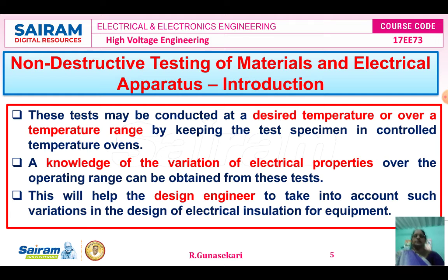These high voltage tests are conducted at a desired temperature or over a temperature range specified as per the standard, by keeping the test specimen in controlled temperature ovens. Then the knowledge of the variation of the electrical properties over the operating range is obtained from the high voltage test. These tests are very helpful to the design engineer, to take into account the variation in the design of electrical insulation for electrical equipment.